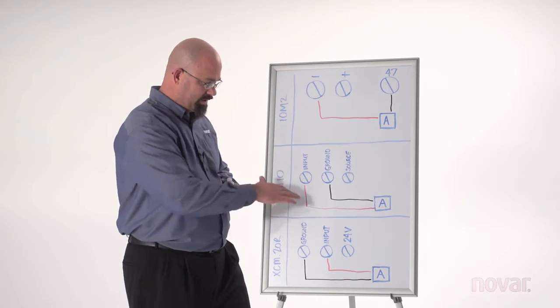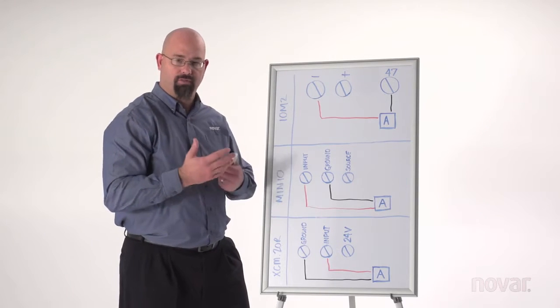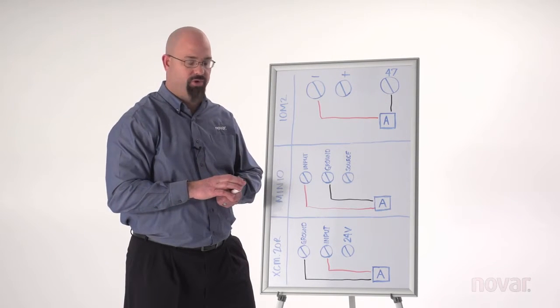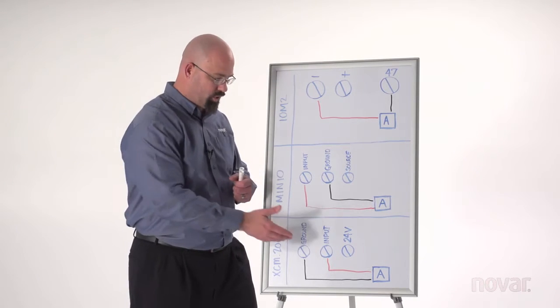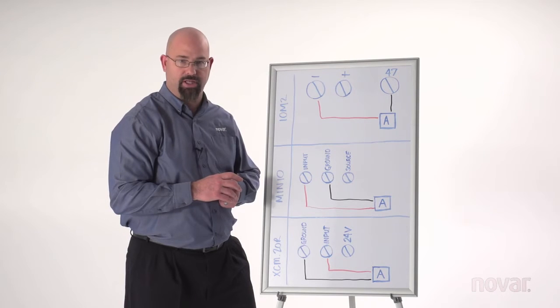Now with the XCM-20R it's compatible the same with the MIN-IO: 4 to 20, 1 to 5 or 0 to 10. It's just here that's all software selectable so there's no jumpers for you to move for each independent input.